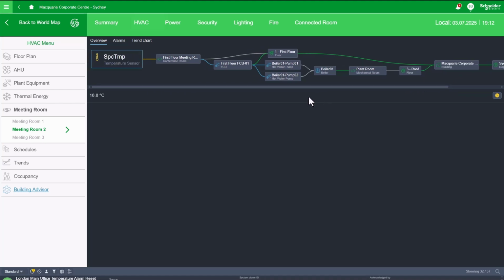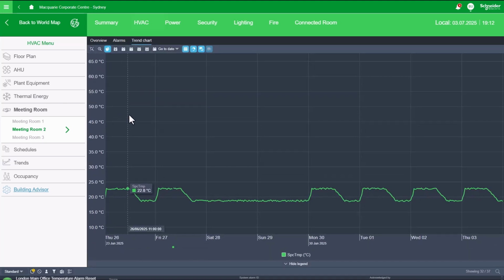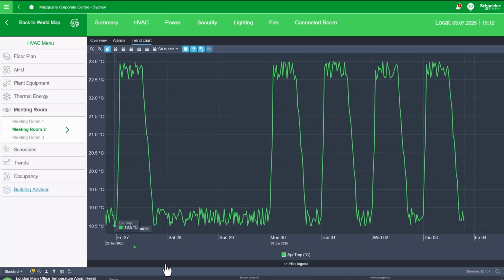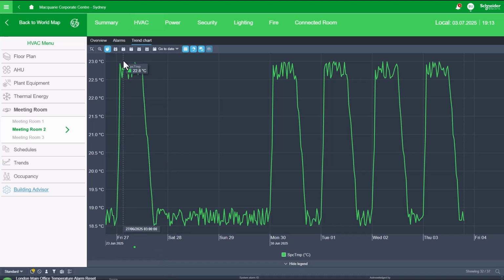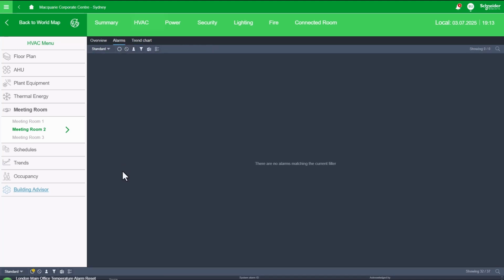With the temperature point selected, the semantic view automatically displays any associated trend charts and active alarms. I click on the trend chart to view the historical data for the sensor. Next, I check the Alarms tab. There are no active alarms for this point.